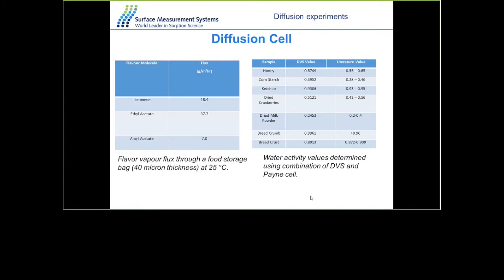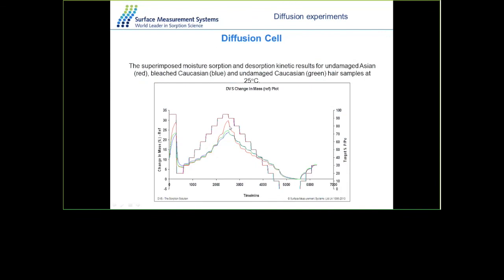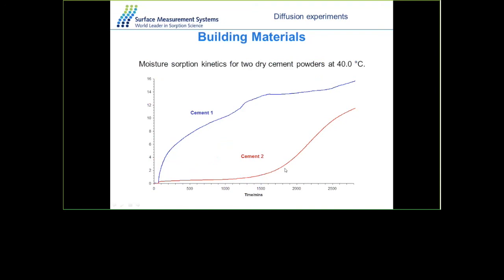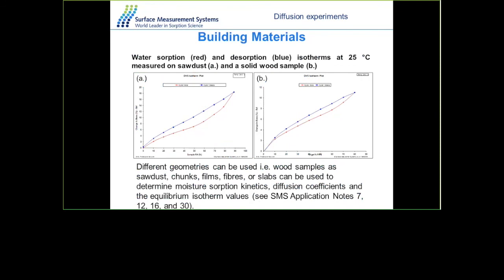A typical example is limonene, ethyl acetate, or amyl acetate — flavoring materials that can pass through food packaging — and the same technique can be used to measure water activity for food materials. We have tested a series of food materials including honey, cornstarch, and ketchup, with values in very good agreement with literature. For hair, damaged, bleached, or heat-treated hair can all be distinguished by differences in mass uptake. For building materials, one type of cement picks up moisture very late while another does so very quickly, revealing shelf life and stability differences.